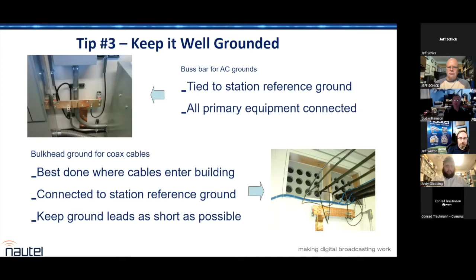Remember, with lightning protection, we're playing a voltage divider game. You start at the antenna, you head back, and you look for places for that lightning energy to go. And if the easiest path is through your equipment, you're going to replace a lot of stuff on a regular basis. This is physics. We can't stop lightning, but we do have a fair bit of control over where it goes, and that's done purely by how we do our grounding and how we install our surge protector. Adding the ferrites, again, icing on the cake, but on its own, it's not going to do a whole lot.